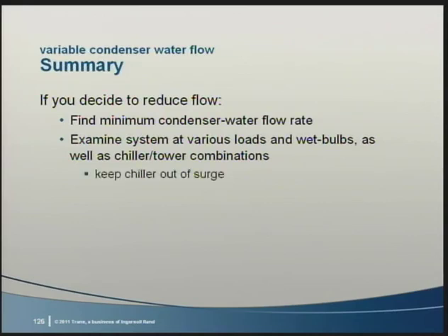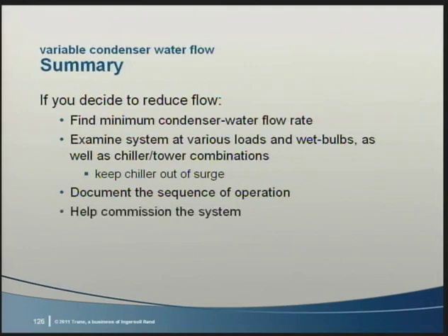One reason to study the system is to keep the chiller out of surge and thereby allow it to meet the cooling load. This is especially important at wet bulb temperatures closer to design. Once you've done this work, write a detailed sequence of operation. Finally, there's no replacement for being out at the job site with a system operator and seeing what happens during operation. Consider being part of the recommissioning team.